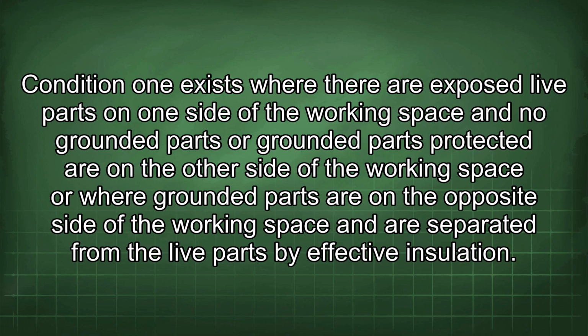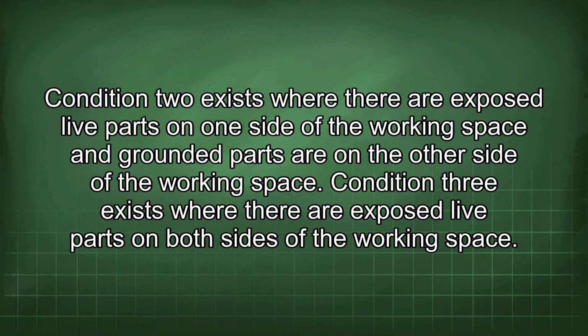Condition 1 exists where there are exposed live parts on one side of the working space and no grounded parts, or grounded parts protected, are on the other side of the working space, or where grounded parts are on the opposite side of the working space and are separated from the live parts by effective insulation. Condition 2 exists where there are exposed live parts on one side of the working space and grounded parts are on the other side of the working space. Condition 3 exists where there are exposed live parts on both sides of the working space.